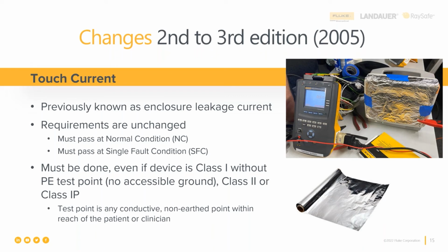We're going to test this in normal condition, normal polarity and reverse polarity. We're going to perform the single fault tests: first open the neutral or L2 and then restore that and open the ground. And we're going to see what is the worst case leakage current and under what condition we find that. It has to be done. So this is an example of how you do that.